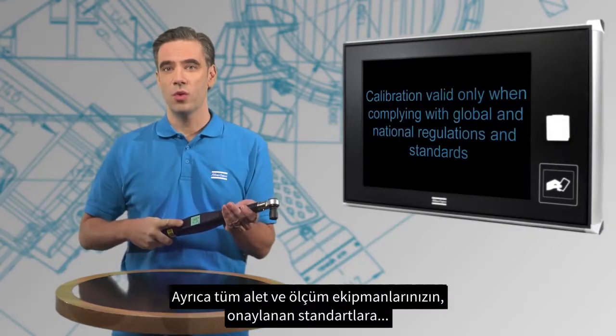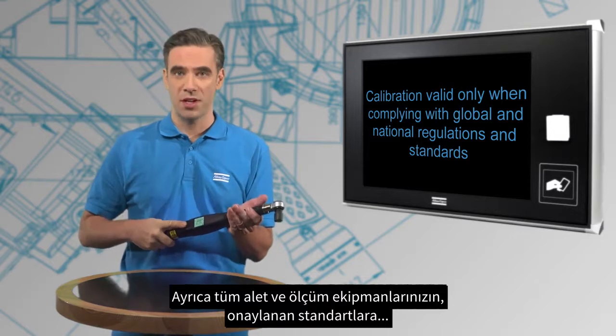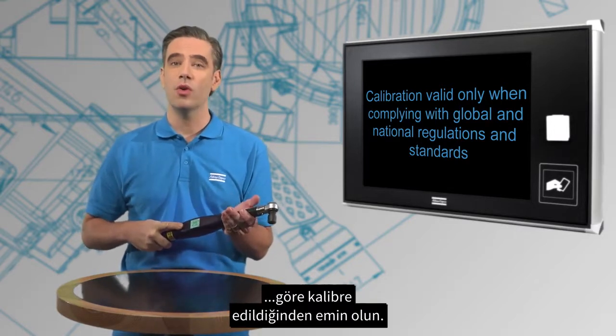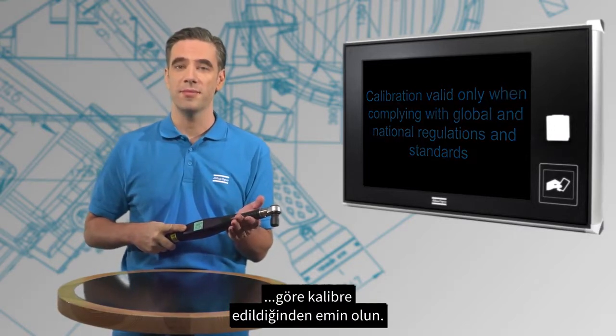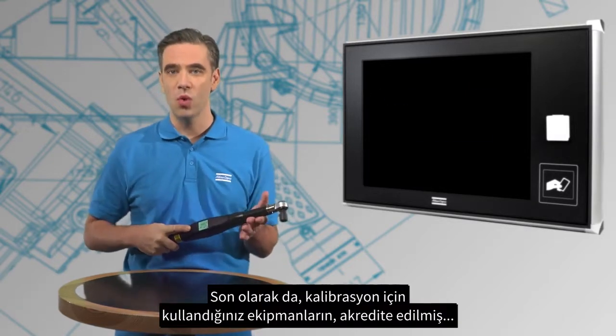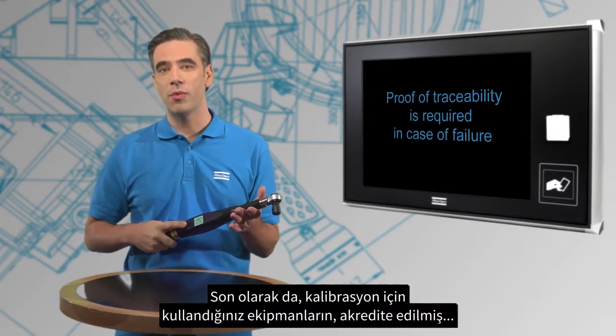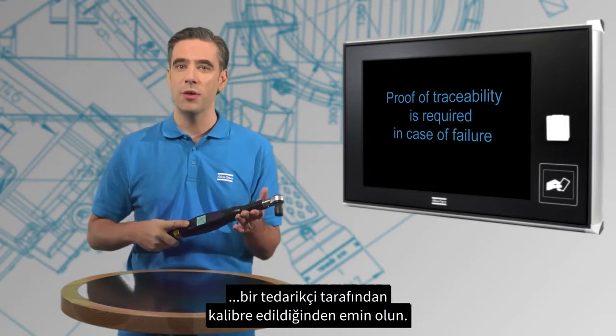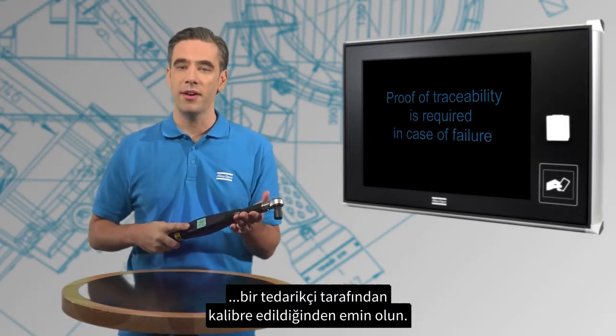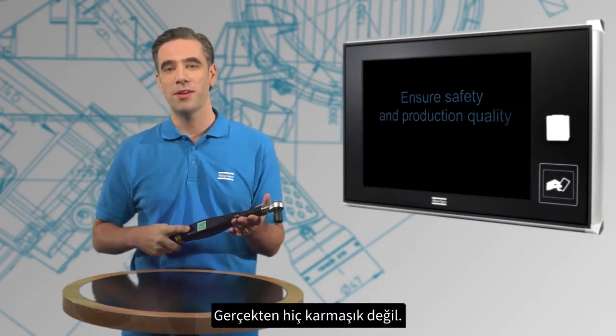You should also make sure that both your tools and measurement equipment are calibrated according to the approved standards. Finally, you need to make sure that the equipment you use for calibration is also traceably calibrated by an accredited provider. Really, it's not that complicated.